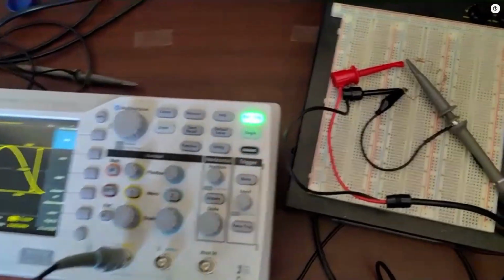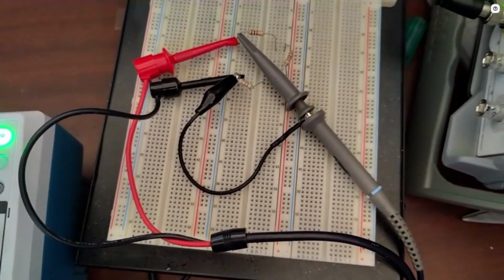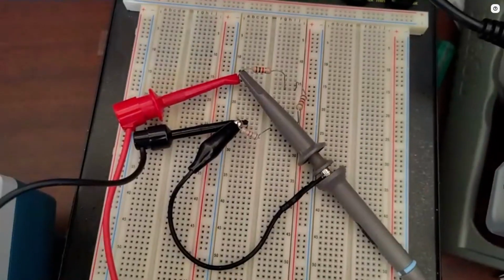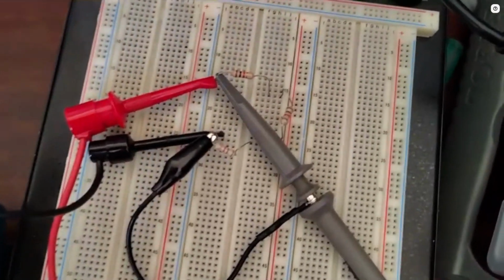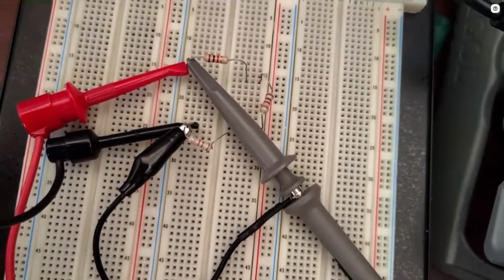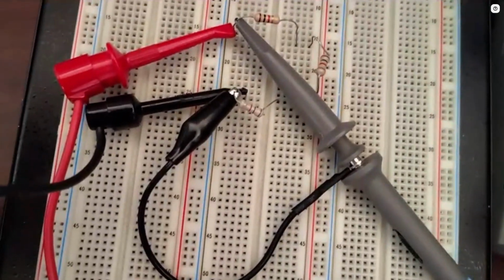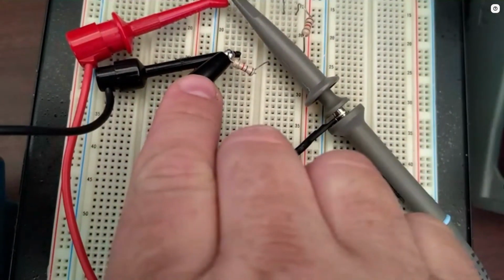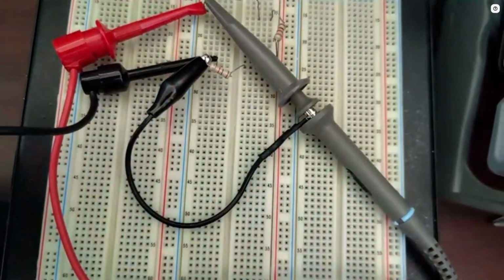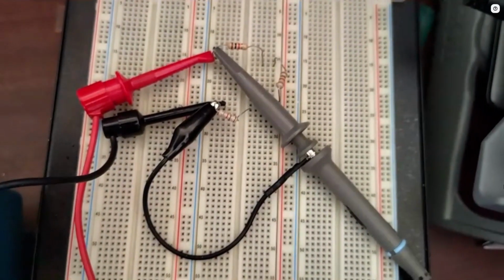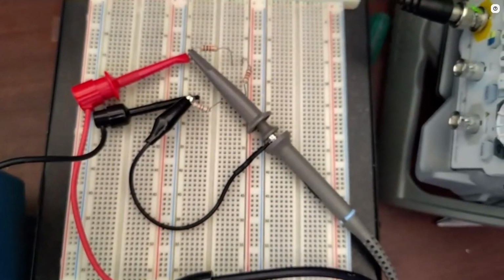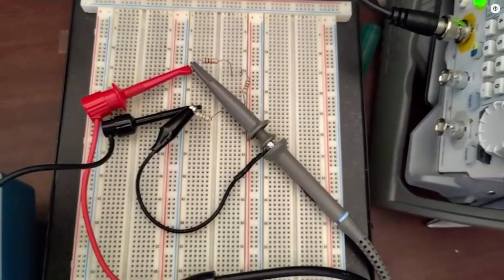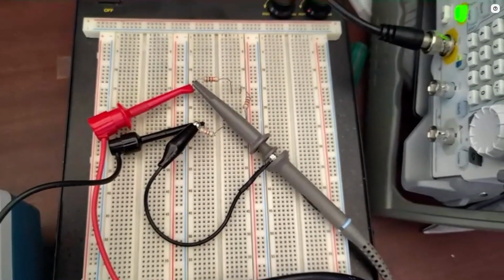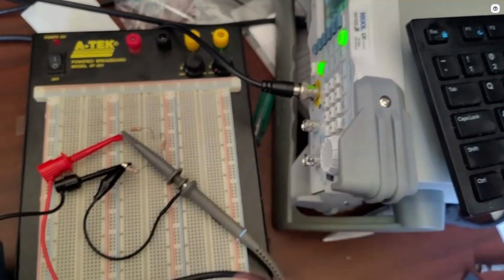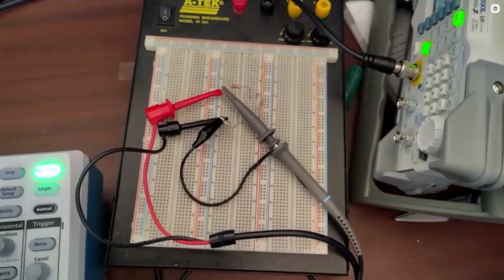All right. We're going to bring it back down and take a measurement. One of the things that we're after now is we need to find out how the oscilloscope measures. Everything has to measure to this common ground point. Without that common ground, the measurements are not going to be accurate because they're going to be referencing a different value. And we want these values all to reference what's coming out of the generator or whatever part of the circuit we're after.